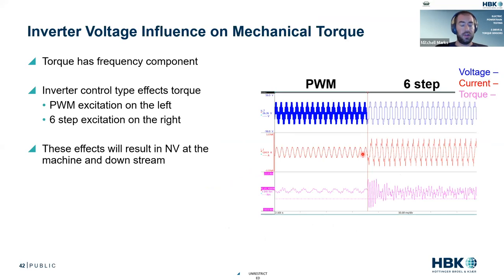And lastly, we can do things like looking at dynamic torque. And here's an example of a machine running under 13 kilohertz pulse width modulation, nice sinusoidal current, torque in pink, that's got some torque ripple, but nothing crazy. And then we change that control. We're recording data the whole time. We go from 13 kilohertz to 6 step. Our current gets all kinds of harmonic content and our torque goes crazy. We can again analyze that electromechanical system. We can see how our inverter affects our torque or noise and vibration or temperature.